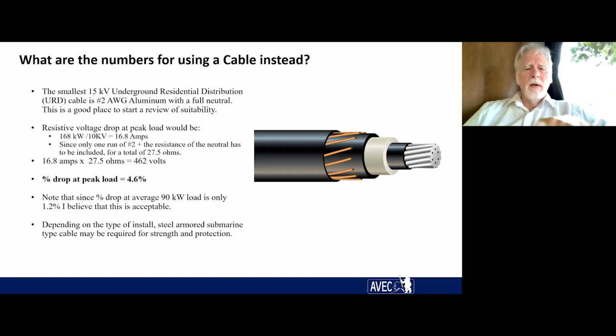So again, crunching through some numbers. This is just Ohm's law stuff, nothing fancy. If we put a single line of this rather inexpensive URD between Shugnak and Kobuk, we would have a voltage drop at peak load. This non-occurring peak load that we got in 2022, which was 168 kW, we would have 4.6%. So that's quite a bit higher. That's double what we had in the last slide. But you've got to remember that's peak load.